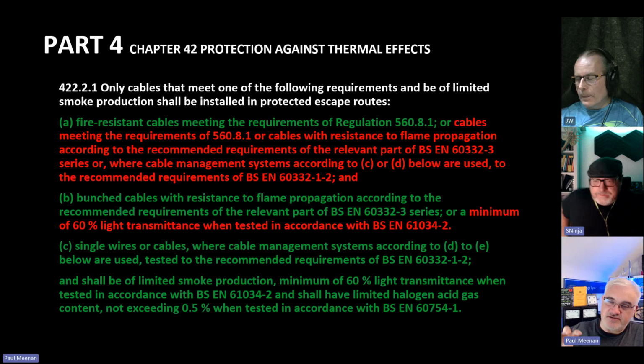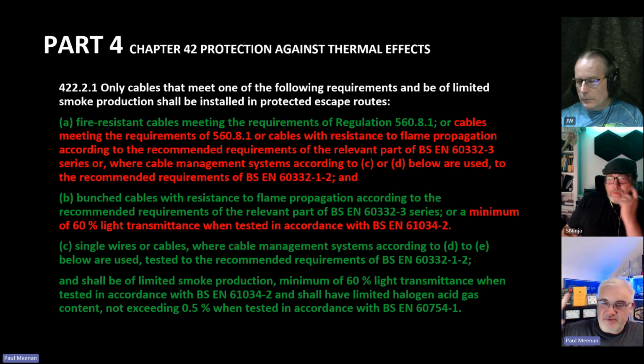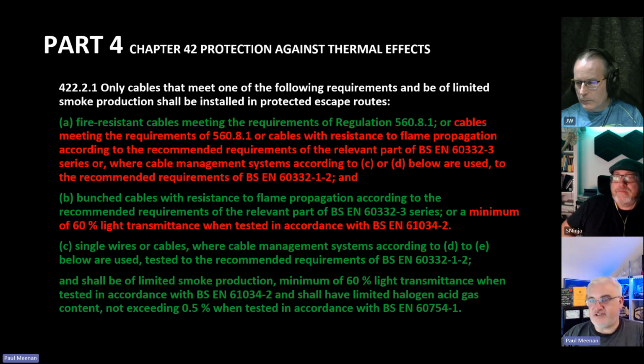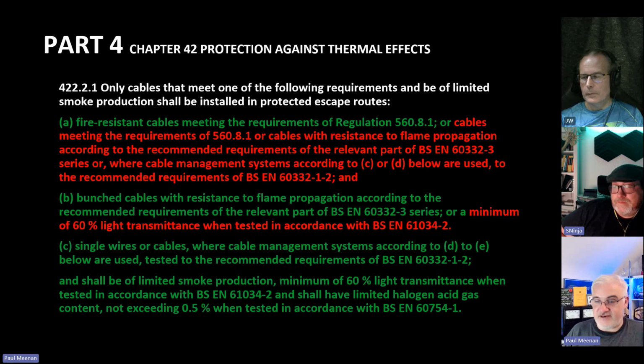We'll come on to this later, because most people will talk about Approved Document B building regulations - that's where most people start. If they can't get Approved Document B compliance, as Dan will say, they'll move into BS 9999. If it's the domestic world, it's BS 9991. If it's railways, it's 9992. And if they still can't do that, it's 7974, a quantitative risk analysis, which is a whole series of standards Dan can talk about.